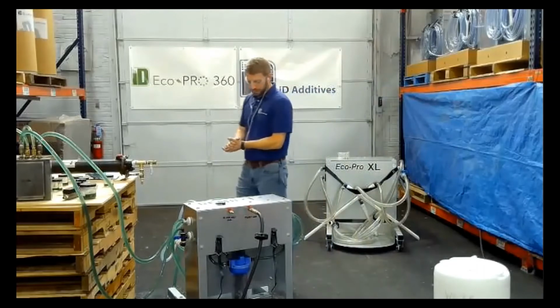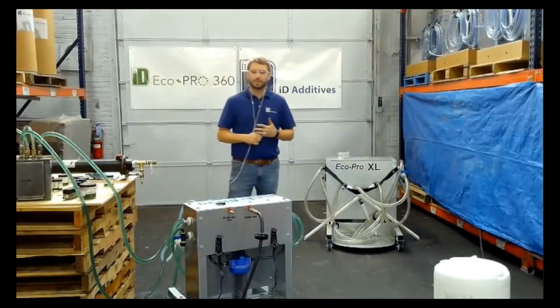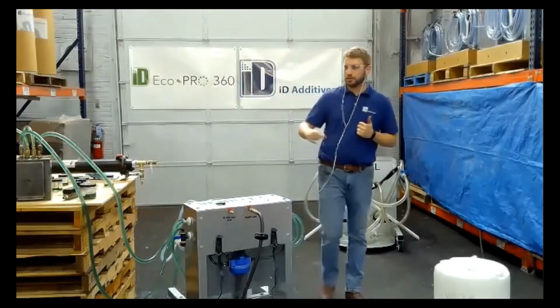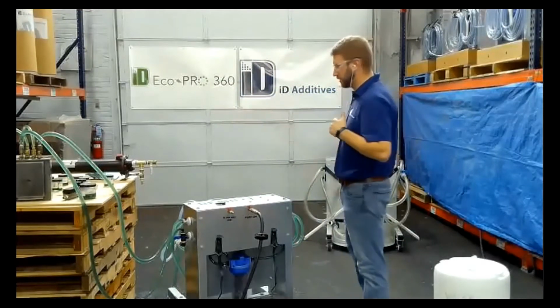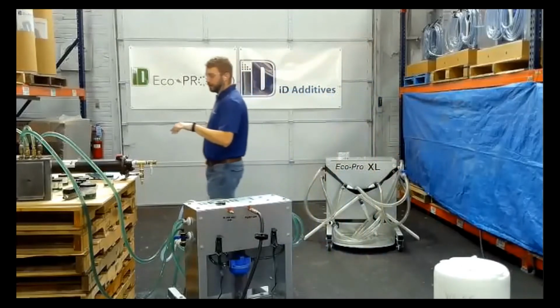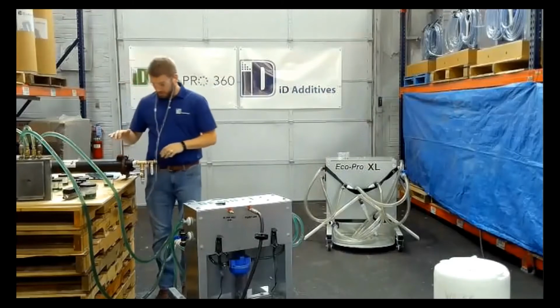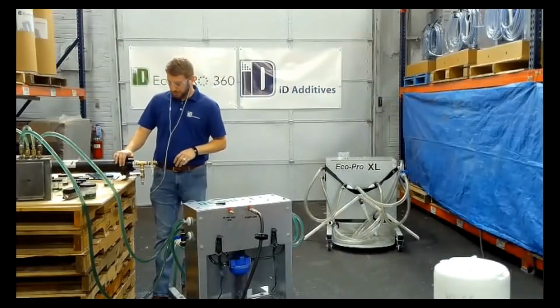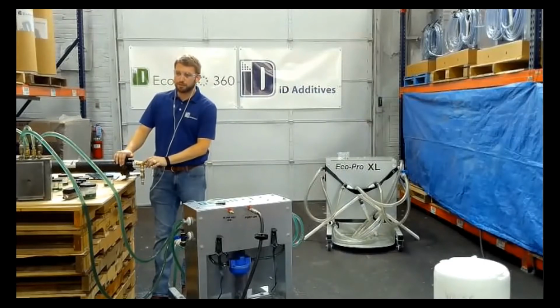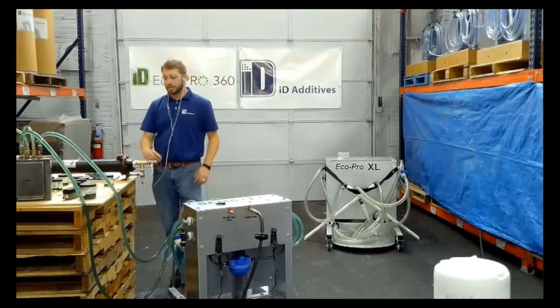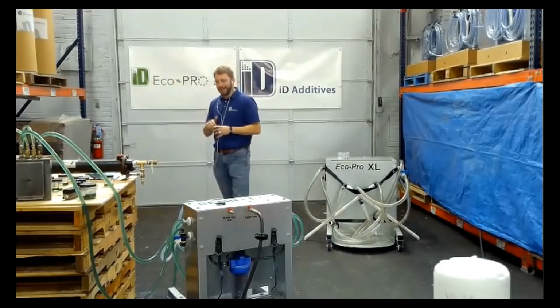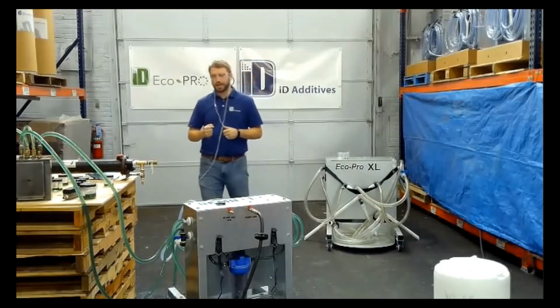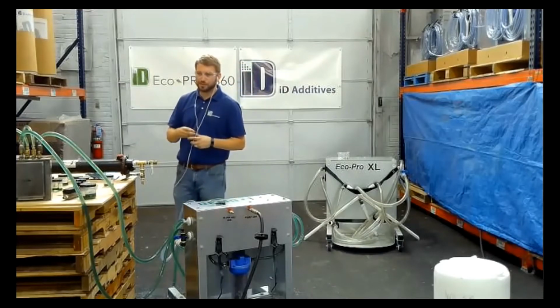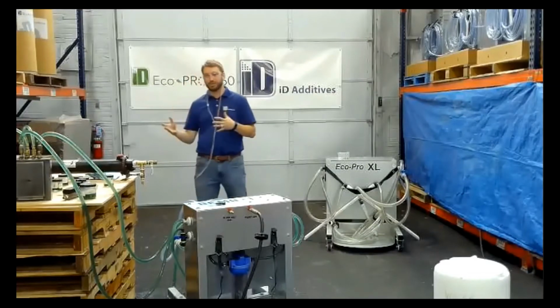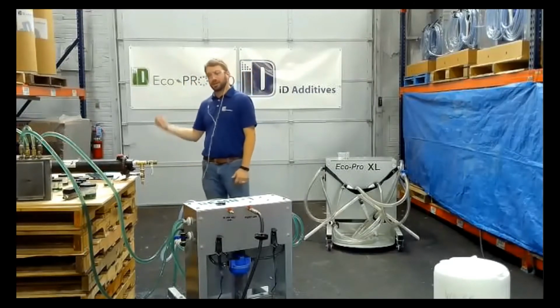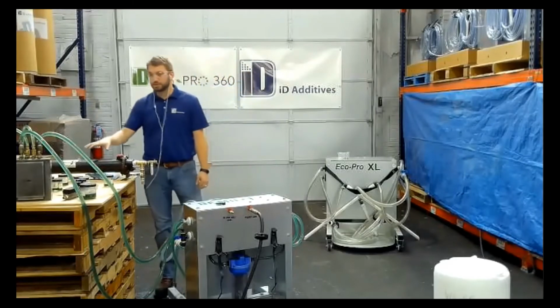It's safe to work with. We use it to remove rust, calcium, and lime scale on various pieces of equipment, whether it's an injection mold or cooling passages like we have hooked up right now. Earlier we demonstrated plumbing into a heat exchanger, which if you're not in maintenance, just go talk to your maintenance guys - they'll tell you how big a pain it is to pull off a heat exchanger and then rod out the copper tubes on the inside. Copper is a very soft alloy, so sometimes you puncture it and have to drop a sleeve in, and it's very tedious. A lot of guys roll their eyes, or they just chuck the thing out and buy a new one. This is a smaller tube-style heat exchanger.